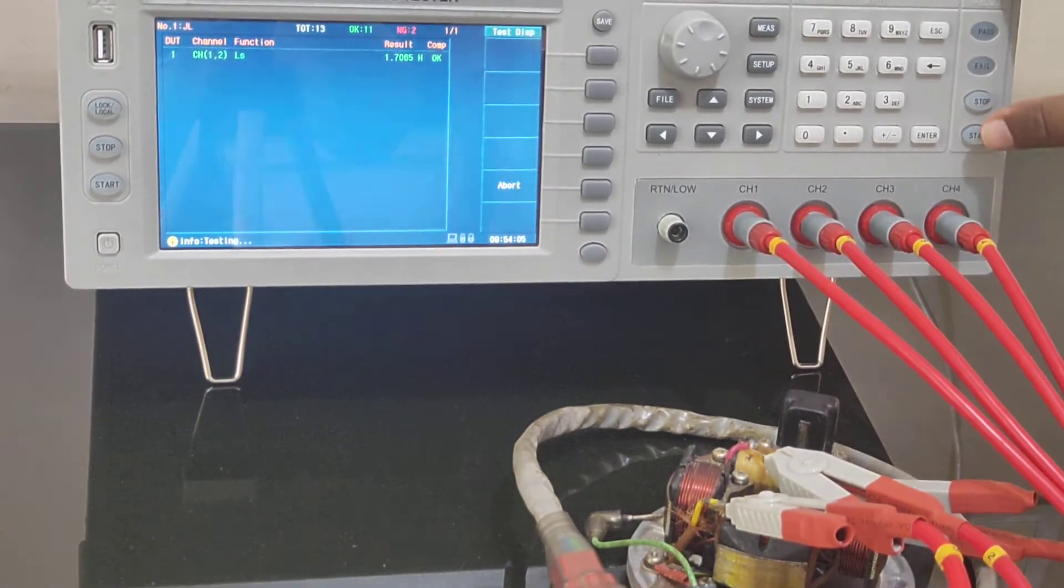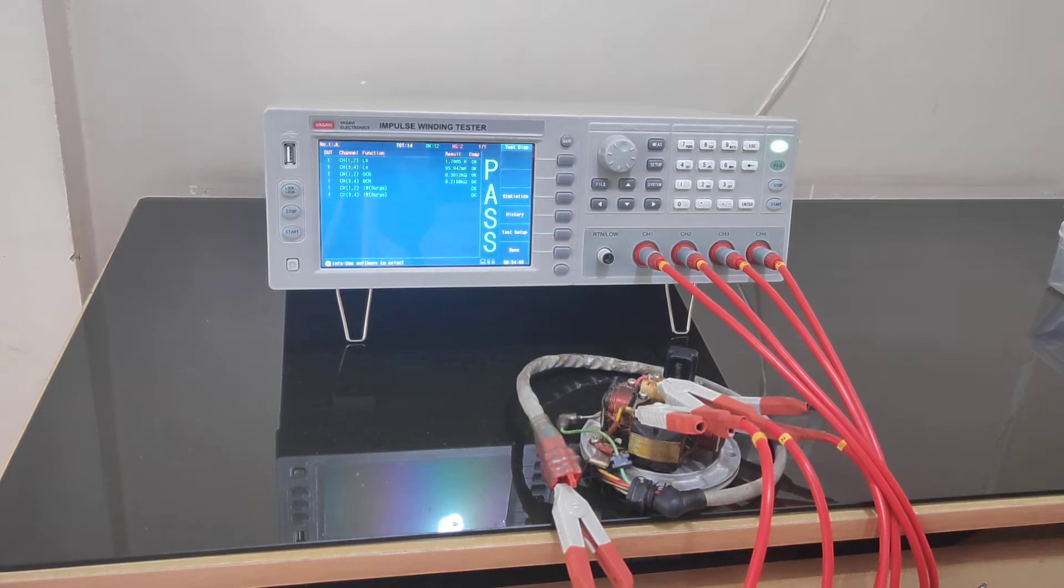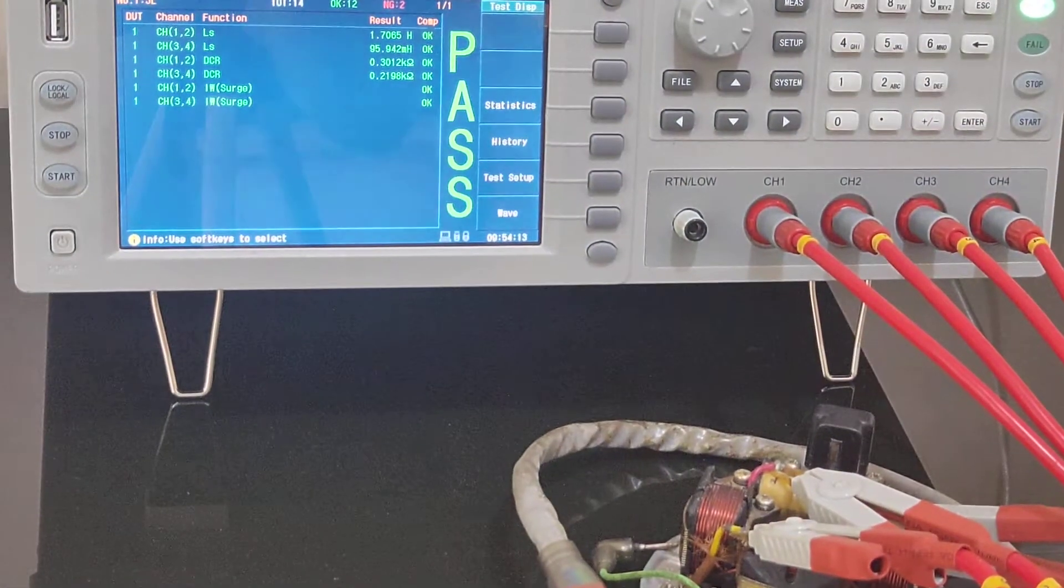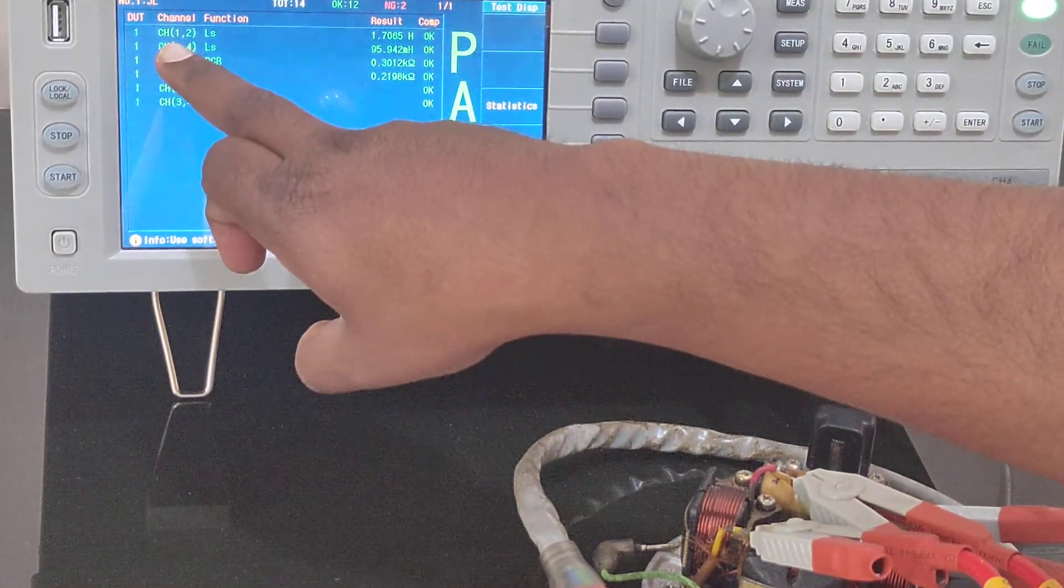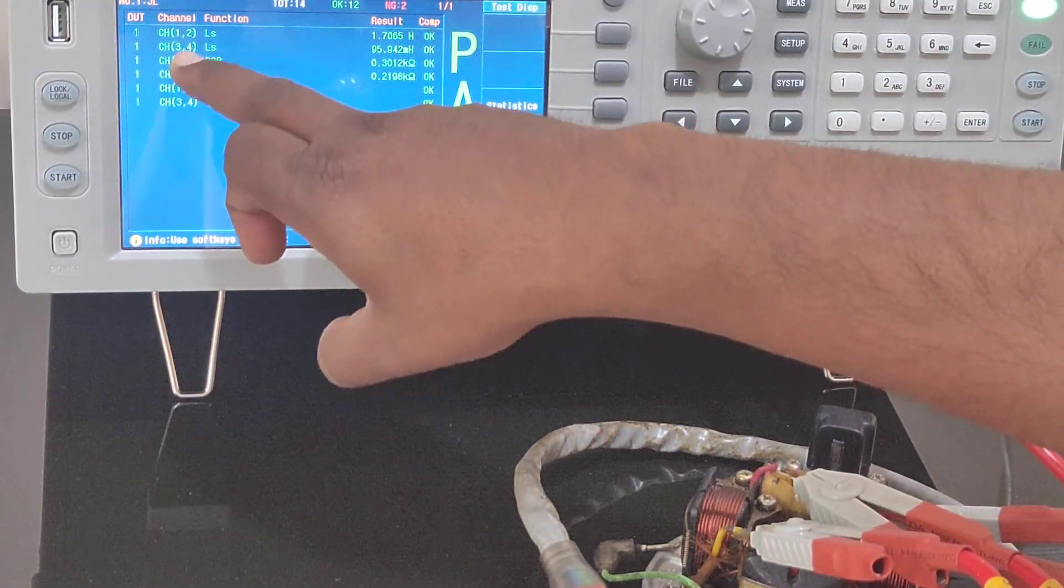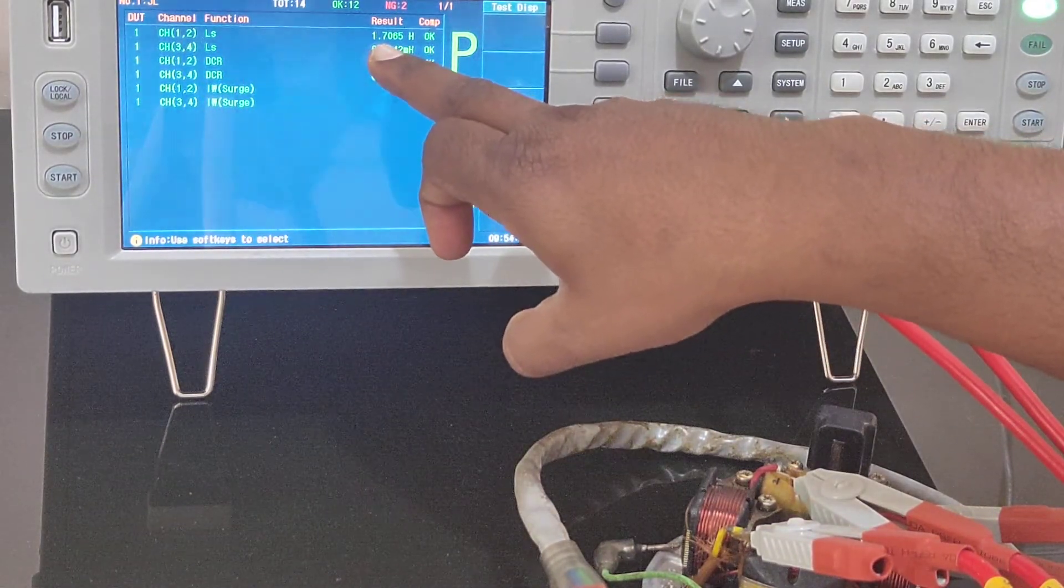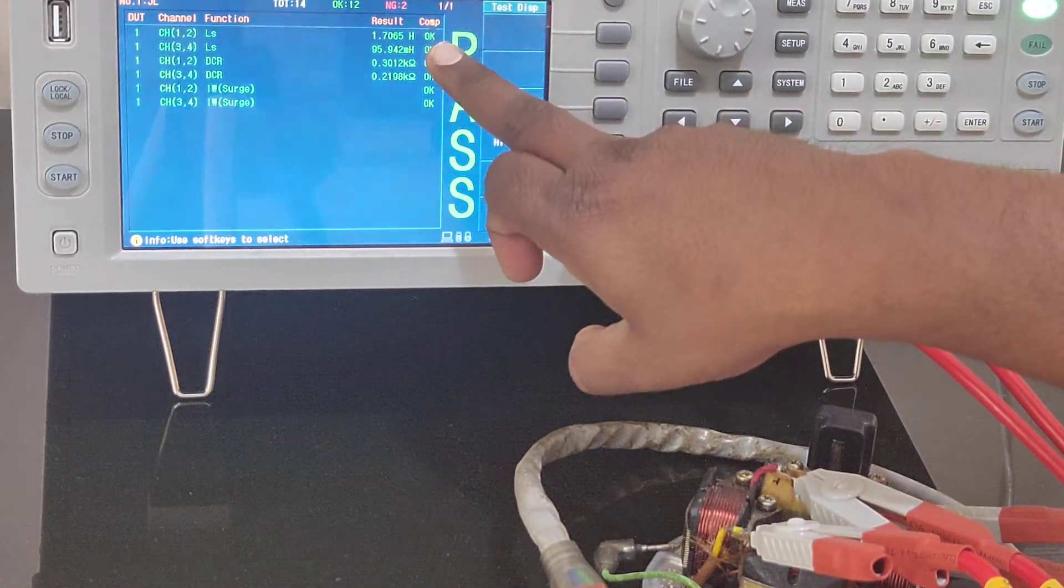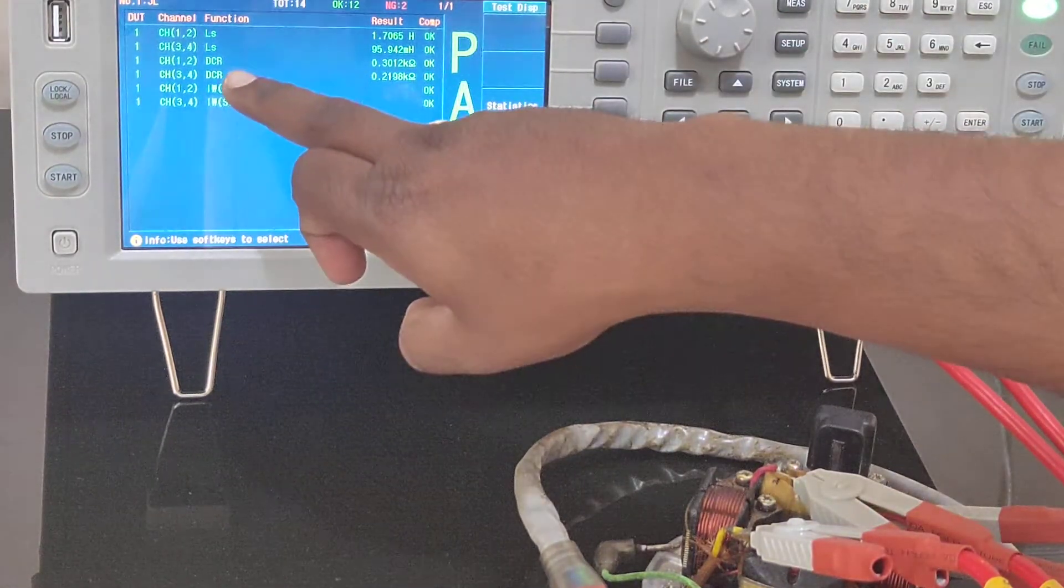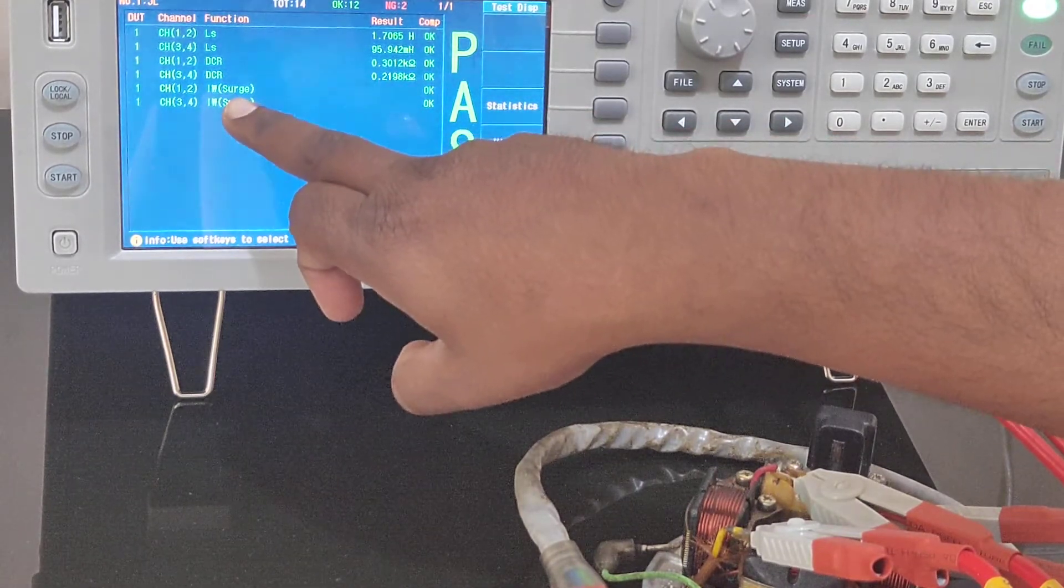It tests, compares with the limits and checks whether it is pass or fail. As you can see here, this is measuring inductance between channel 1 and 2. This is the measured inductance. In case if it is within the tolerance it shows okay.